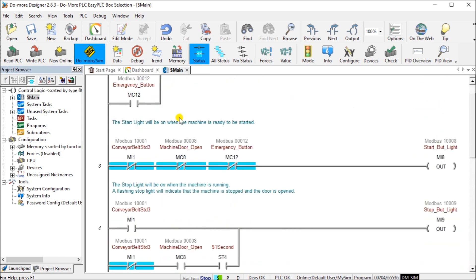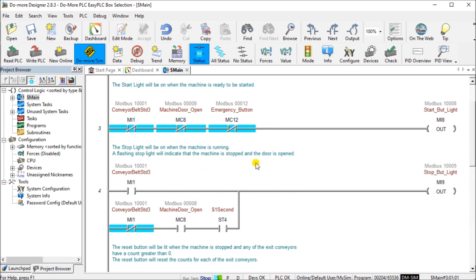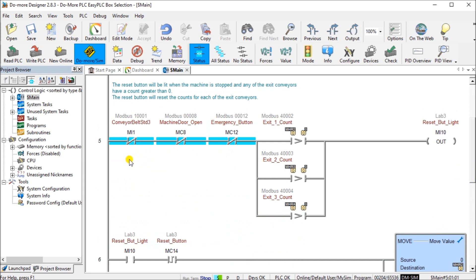If the conveyor resets, we have to go back and start again to resume the process. When the conveyor belt is not running, door is not open, and no emergency stop, the start button light will illuminate to indicate to the operator that the machine can now be started. When the conveyor belt is on, the stop button light will be on. If the conveyor is off and the door is open, we use a one-second pulse to flash the red light, indicating the door is open.